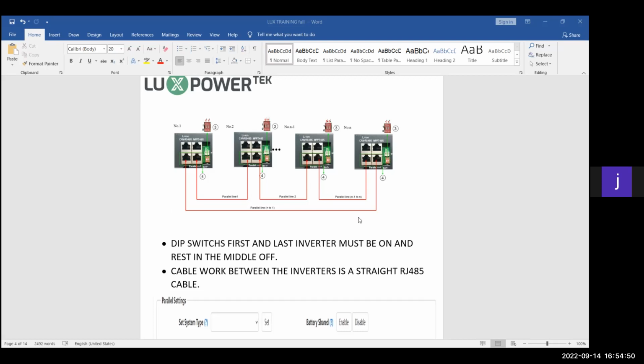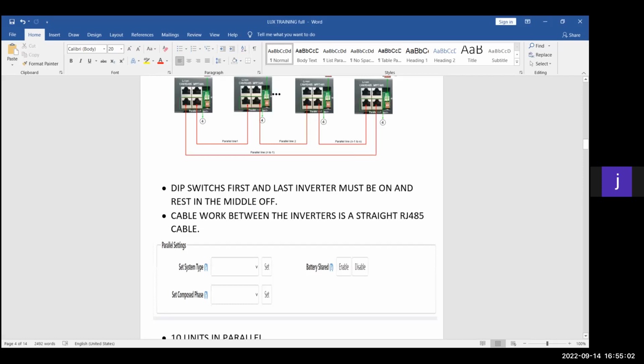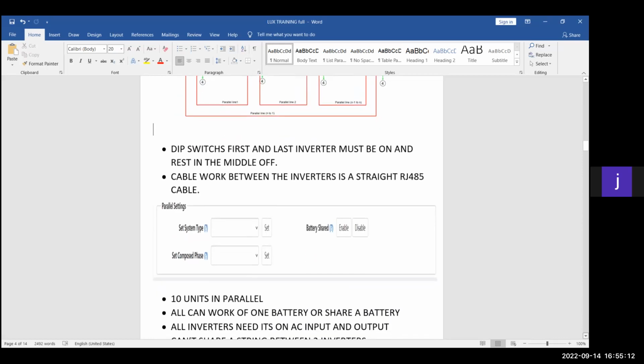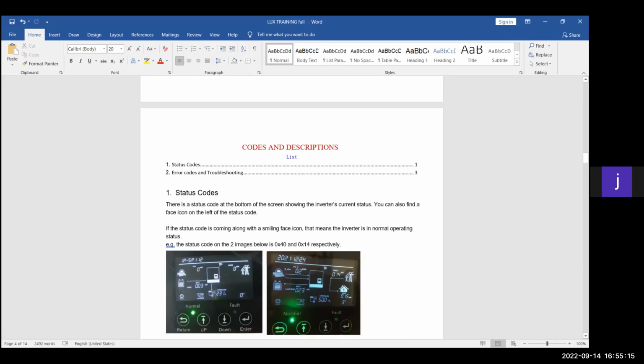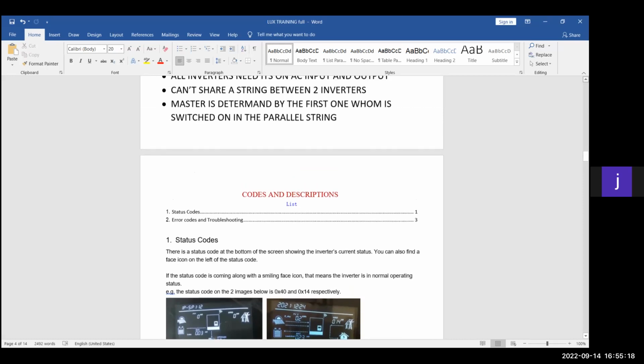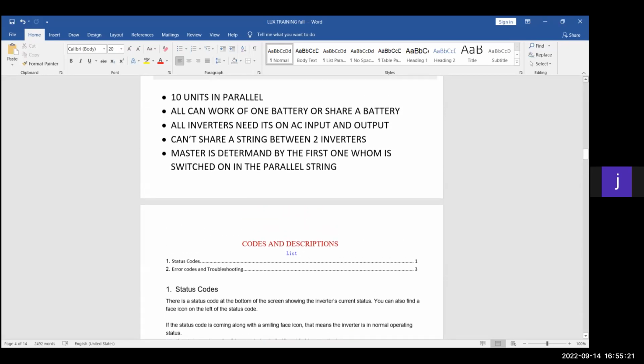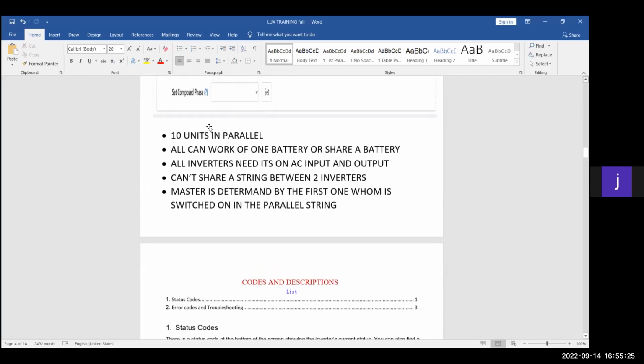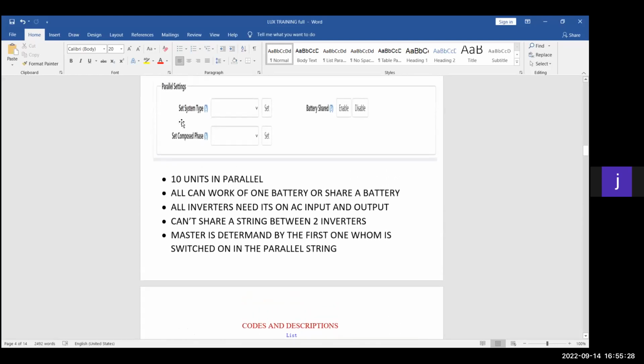Okay, I'm going to go slightly more into this parallel system here. In this instance, you can do the parallel settings on the screen of the inverter or online. I usually quickly go on the screen of the inverter at setting 21. You will be able to do your parallel settings. Let's just quickly go slightly higher. Okay. So once you see this page online that you have here, you can select system type, that's single phase or three phase. Parallel, then set composed phase is for a three phase system.